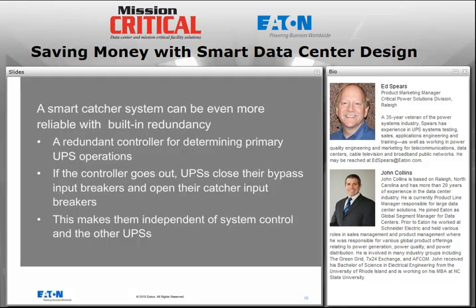So a smart catcher system can be even more reliable than, for example, a parallel system where I have to think about things like synchronization, load sharing, and selective tripping on failures. This gives us a little bit of an enhanced redundancy and a simplicity of both layout and operation. A couple of things here. If further redundancy is desired, and most clients do, the controller, the brain that handles the decision making here, can be made redundant, and the harnessing and wiring can be redundant as well.